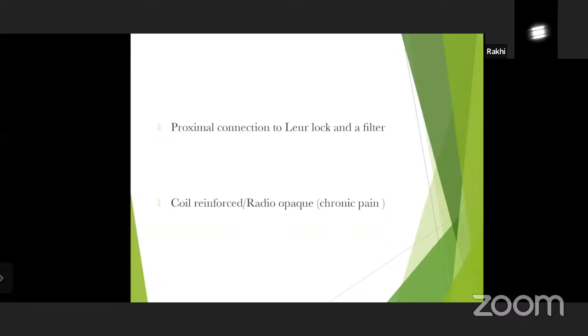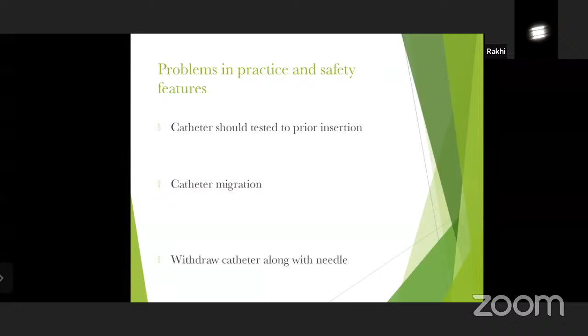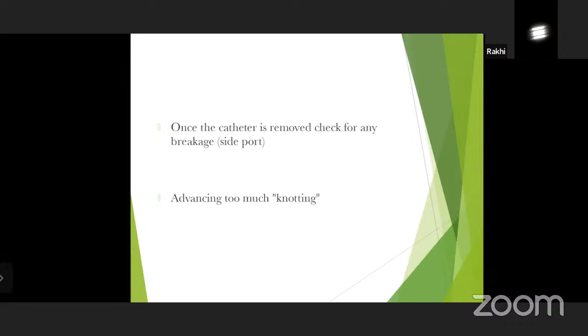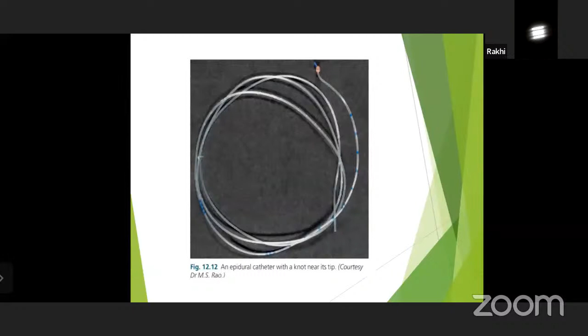The problems in practice and safety features of the epidural catheter. The catheter should be tested prior to insertion, and there's always a chance for catheter migration. So whenever we give a drug through the catheter, always confirm the position of the catheter by giving the test dose. And it's already told that we should withdraw the catheter along with the needle. And once the catheter is removed, check for any breakage at the side port, since the side port is the weakest part of a catheter. And advancing the catheter too much can cause knotting. It's a picture showing the knotting in the tip of the catheter, which was just advanced in the epidural space.